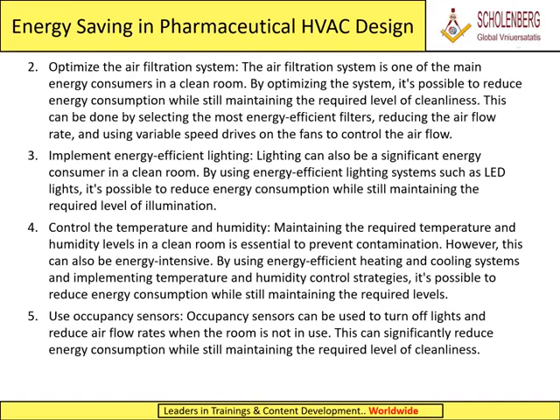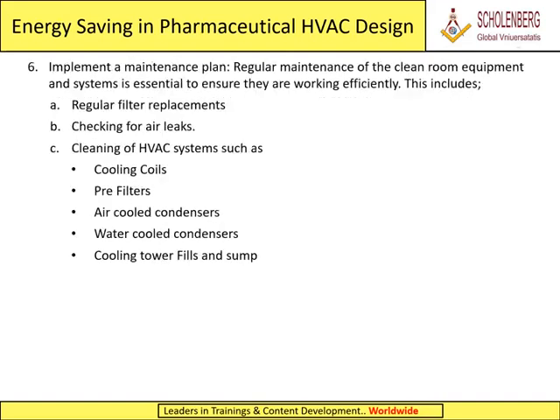5. Use occupancy sensors. Occupancy sensors can be used to turn off lights and reduce airflow rates when the room is not in use. This can significantly reduce energy consumption while still maintaining the required level of cleanliness. 6. Implement a maintenance plan. Regular maintenance of the clean room equipment and systems is essential to ensure they are working efficiently.